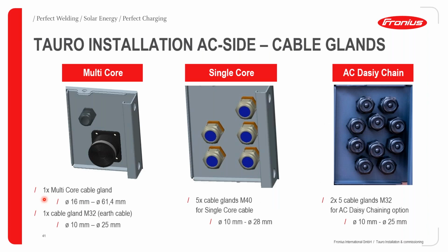With the Tauro installation on the AC side, we have different types of cabling or cores, as my colleague David also spoke about earlier on. The first option you can order with this inverter is a multi-core. So if you have a multi-core Fronius Tauro, this is how the AC will look at the bottom of the inverter. The multi-core cable gland will allow a diameter of 16 millimeters up to 61.4 millimeters. And we'll also have the earth cable, okay, connection, which is that point over there. And this will be from 10 millimeters diameter to 25 millimeters.